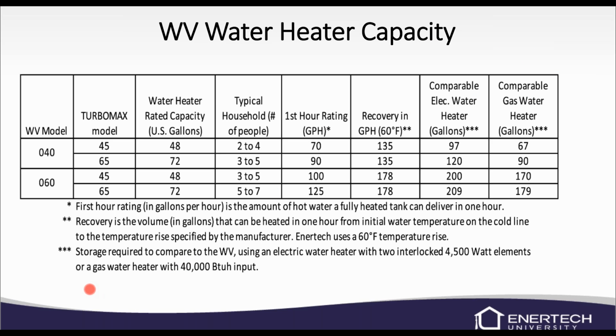This is with the domestic hot water option. We have to use a certain tank. That tank is called a TurboMax tank, and it's built for heat pumps. So basically what we have is a coil inside of a tank. The domestic hot water for your home runs through a copper coil that's inside the tank. The WV supplies bulk load water to the outside of that coil, inside of that tank jacket, and heats that water for the domestic. So we have 2 tanks available, the 45 and the 65 gallon tank.